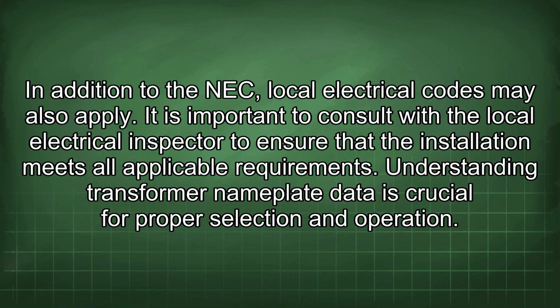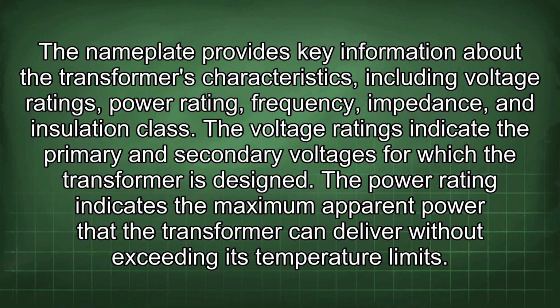It is important to consult with the local electrical inspector to ensure that the installation meets all applicable requirements. Understanding transformer nameplate data is crucial for proper selection and operation. The nameplate provides key information about the transformer's characteristics, including voltage ratings, power rating, frequency, impedance, and insulation class. The voltage ratings indicate the primary and secondary voltages for which the transformer is designed.